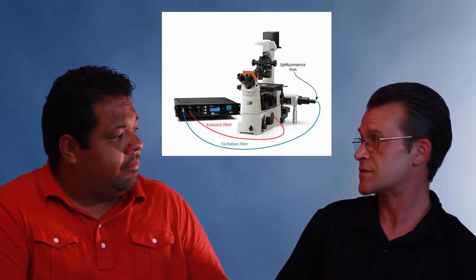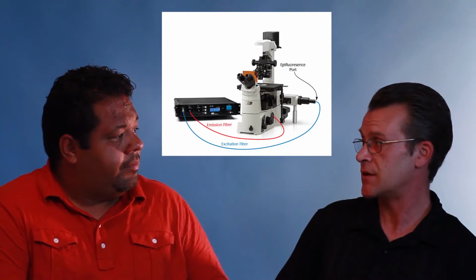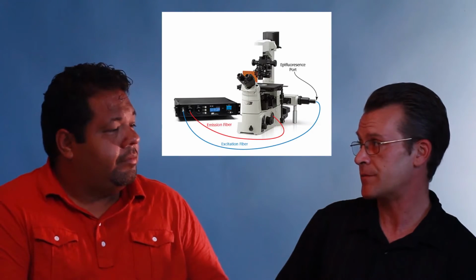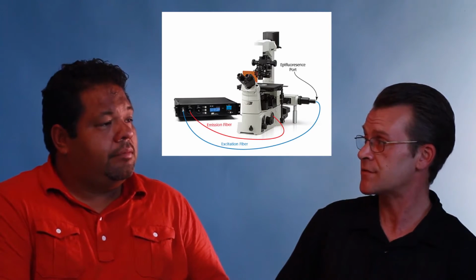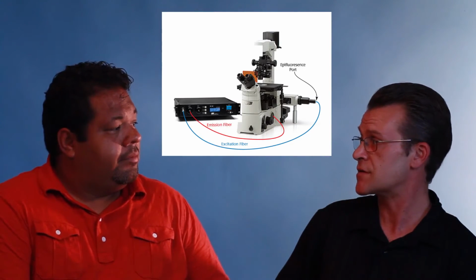Tell me about the microscope. How can we connect this to the microscope? Well, it can be coupled with any microscope as long as the microscope has both an epifluorescence port and an open camera port. So really the manufacturer of the microscope is almost irrelevant as long as it has those 2 features. The output of the biofluorometer, the excitation energy, is going to go out and into an epifluorescence port where it is placed into the microscope optics. From there, the open camera port would be used to collect the emission energy and route it back to the PMTs on the front of the biofluorometer.